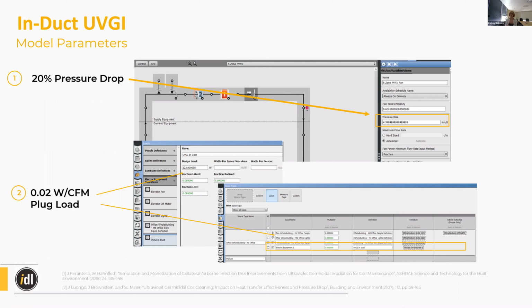We also have to account for the fact that the lamps are there and turned on, and basically are a plug load. So a small plug load is associated with that, but ultimately the pressure drop meant that we had energy savings and not a net positive.